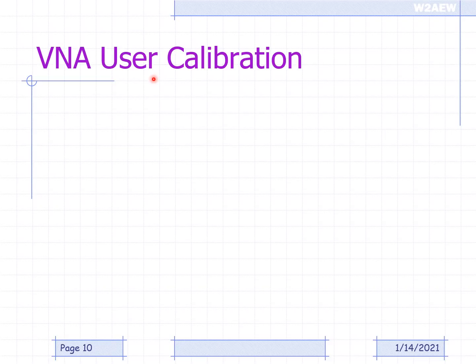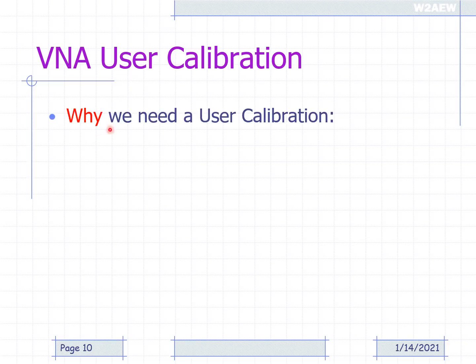You might say, well, I just bought this VNA. Why do I have to calibrate it? Didn't it come calibrated from the factory? Well, the user calibration actually extends what the factory calibration does. And so why do we actually need it? Number one, we're measuring typically pretty large dynamic range. And so what that means is there are very small systematic errors that can't be calibrated out at the factory because they're dependent on how you actually use the device. So we actually have to do them in a user calibration in order to get that good dynamic range and remove those error sources.